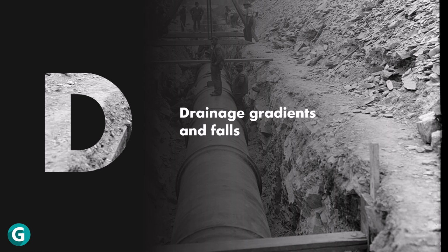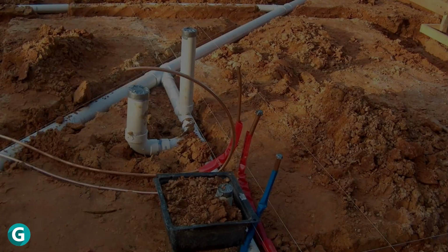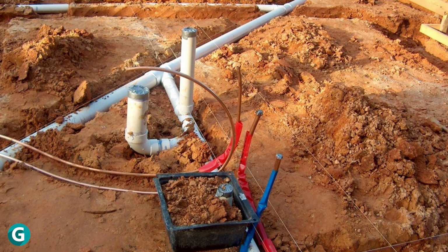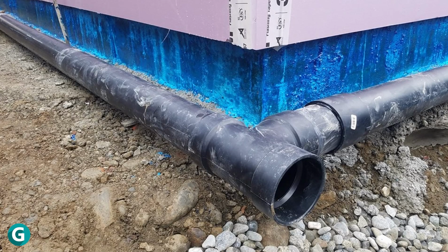For obvious reasons, all horizontal drainage pipes, both above and below ground, should be laid to an adequate gradient. If a drainage pipe is installed perfectly level, the wastewater will slow down and the solids will settle in the pipe, causing blockages. Conversely, if you install a drainage pipe with too much fall, the water in the pipe will flow too fast and leave the solids behind, again causing blockages.